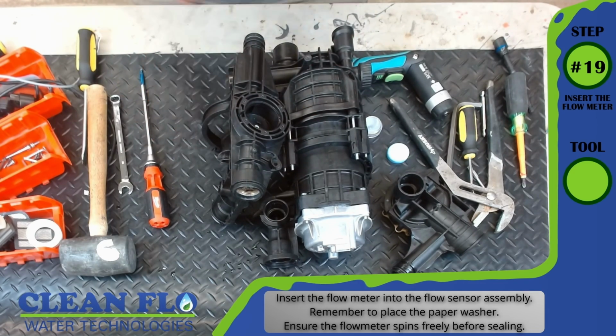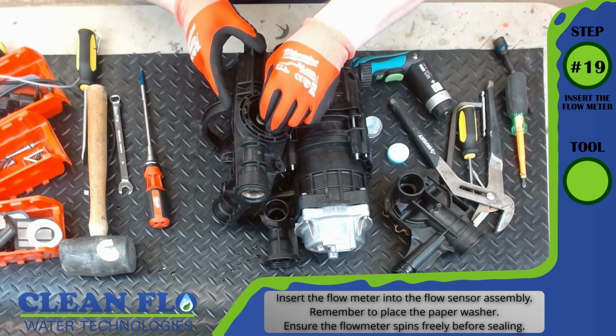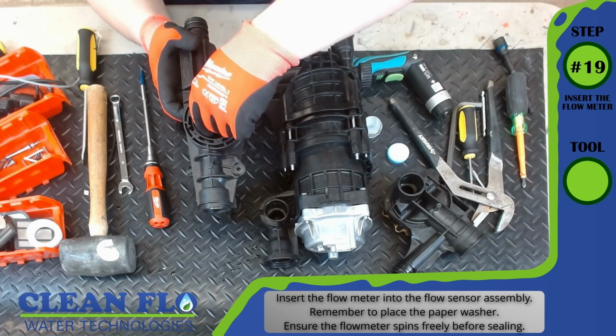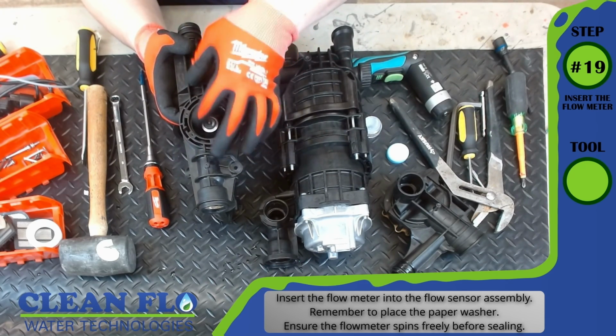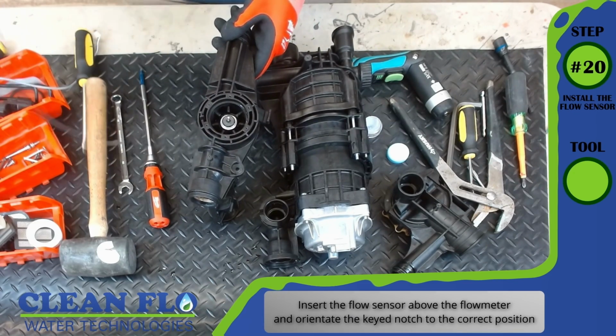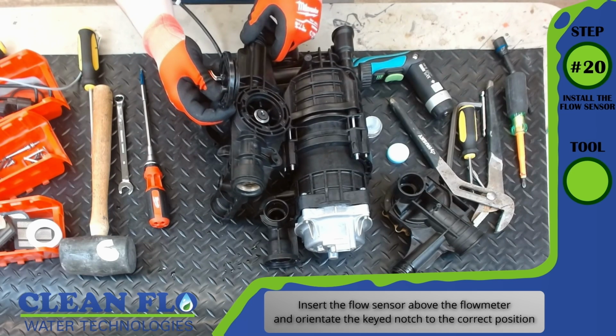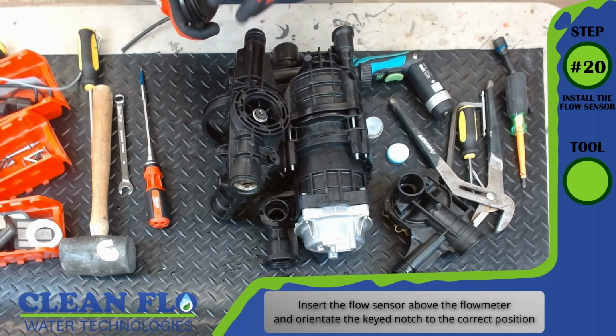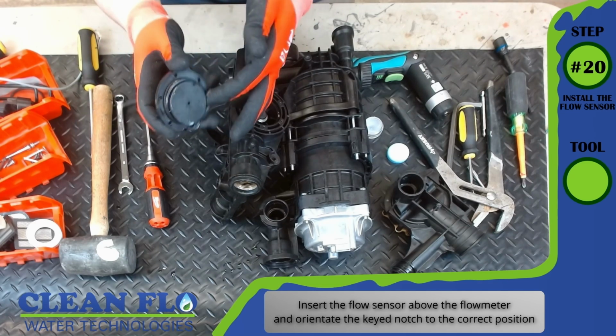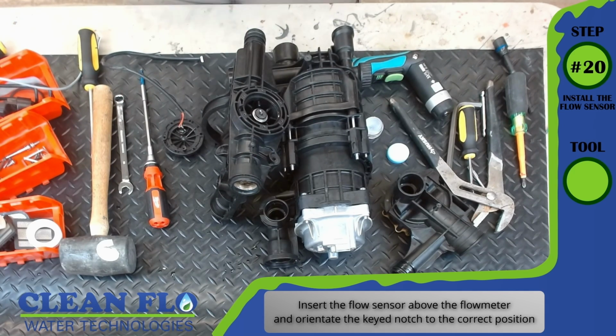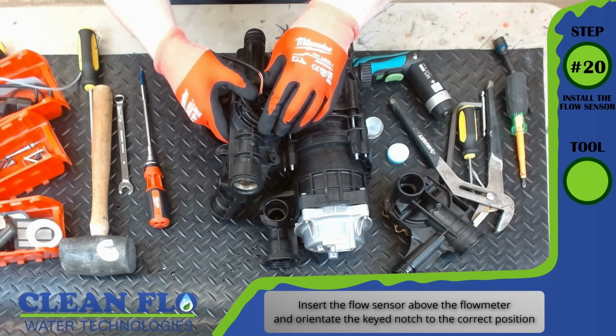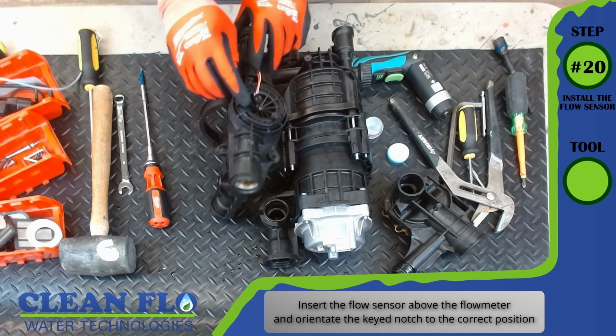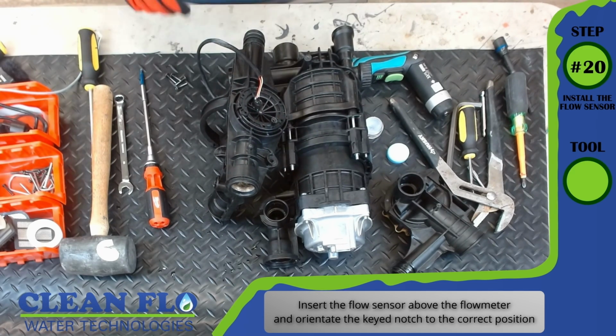When inserting the flow meter, make sure the metal piece with the white dot is facing upwards. Step number 20, install the flow sensor. No tool required. Insert the flow sensor above the flow meter and orientate the keyed notch to the correct position. Make sure that the O-ring is properly lubricated with silicone lubricant, and by supplying small downward force, this flow meter should just snap into place quite nicely. Ensure the key notch matches the flow meter and the body.